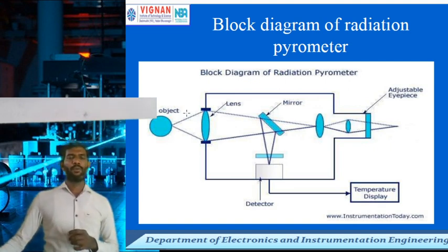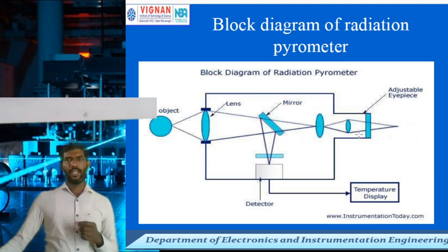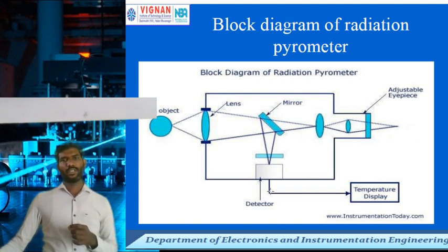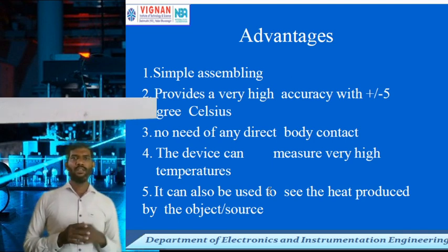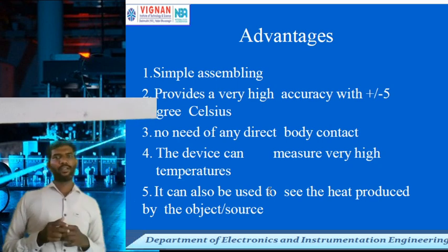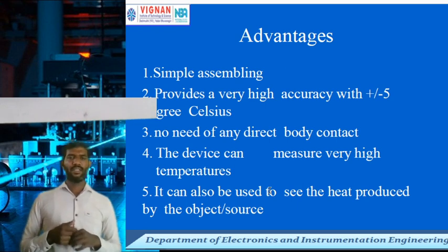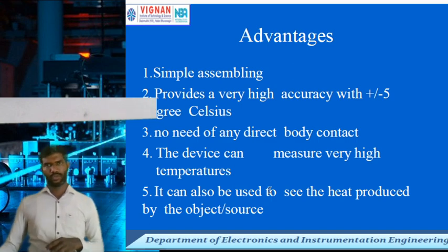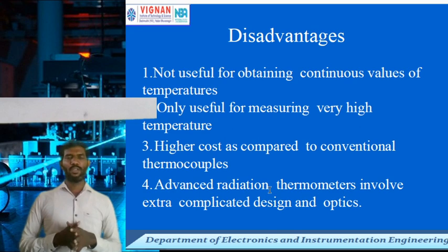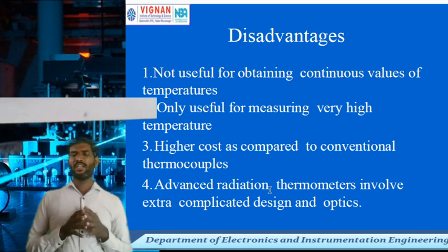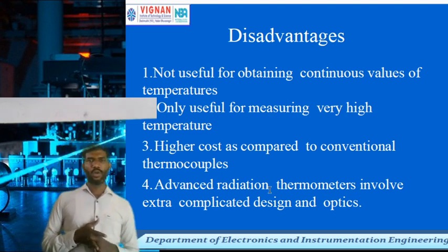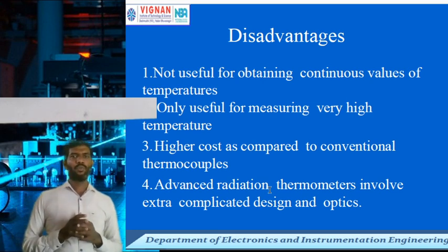The block diagram of the selective radiation pyrometer includes a hot object, lenses, mirrors, and adjustable eyepieces. The temperature is displayed via a detector that receives the different radiation signals. Advantages: simple assembly, accuracy of plus or minus 5, no direct contact with the body required, and the device can measure very high temperatures. Disadvantages: not useful for obtaining continuous values of temperature, only useful for measuring very high temperatures, higher cost compared to conventional thermometers, and advanced radiation thermometers involve extra complicated design and optics.